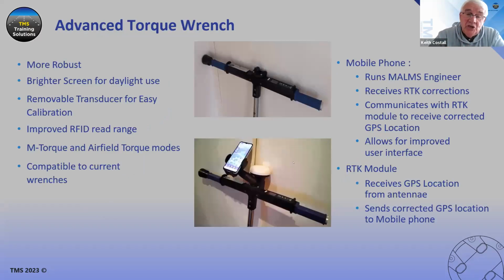Here I mentioned earlier, the torque wrench. The torque wrench itself is for checking the tightness of the bolts we use to secure our light fixtures out in the field, specifically in pavement inset light fixtures that are on the taxiway or on the runway. So there's the new generation of electronic torque wrench. We've had mechanical torque wrenches, we went to electronic torque wrenches, but now we're in the advanced torque wrench era.